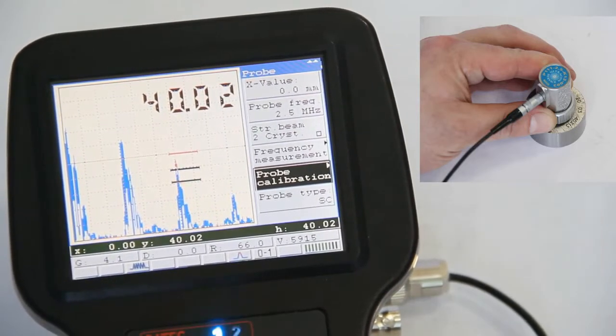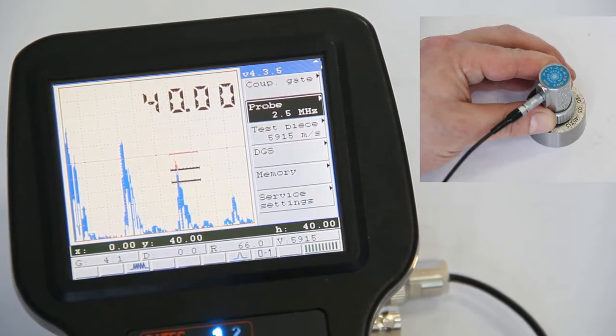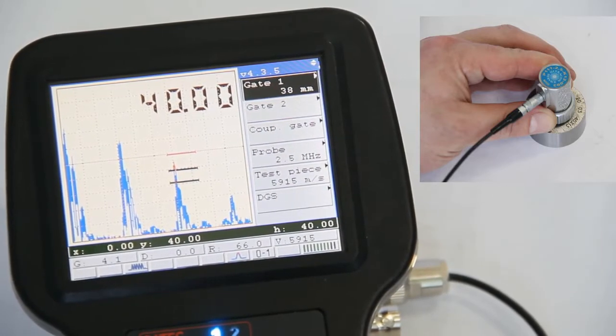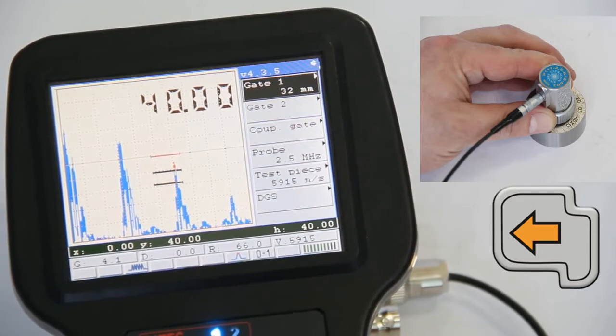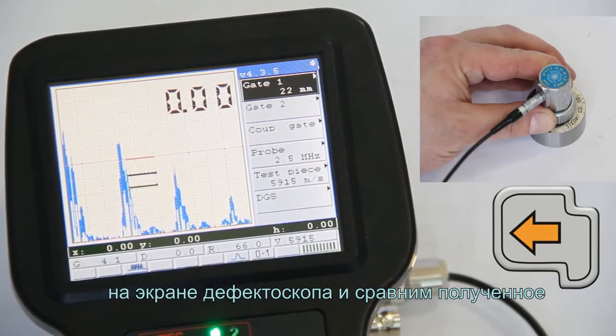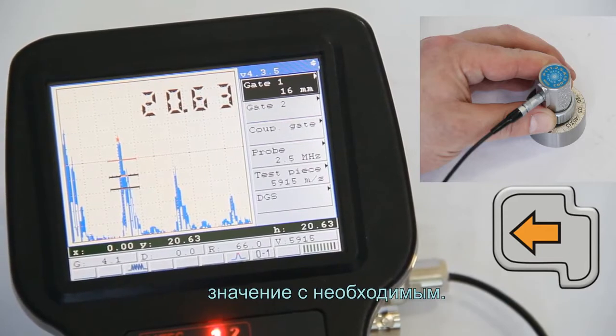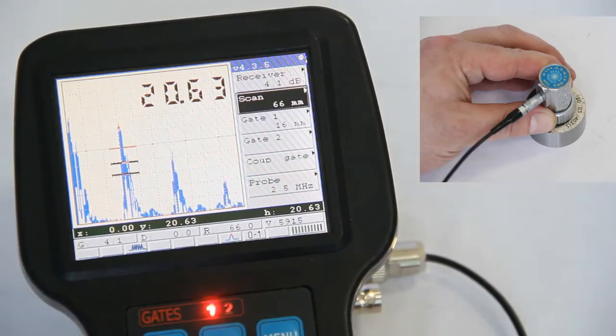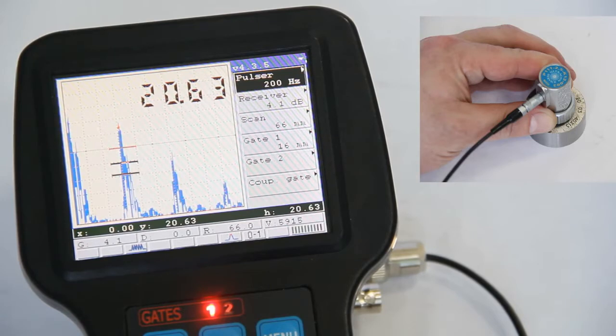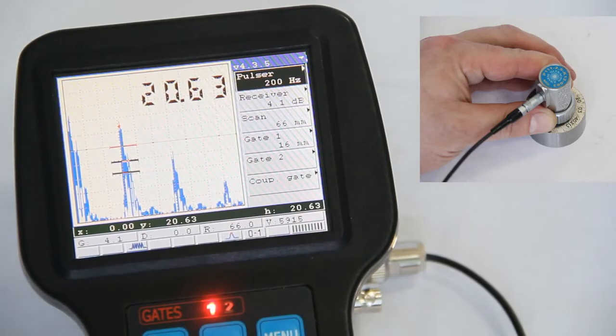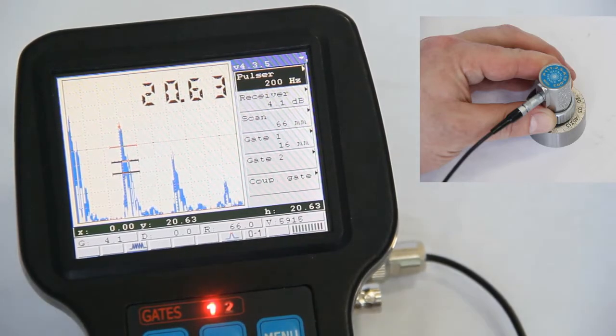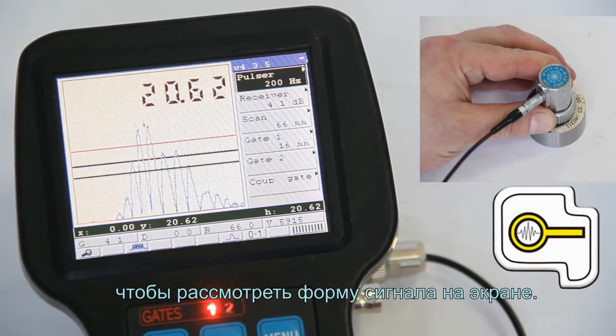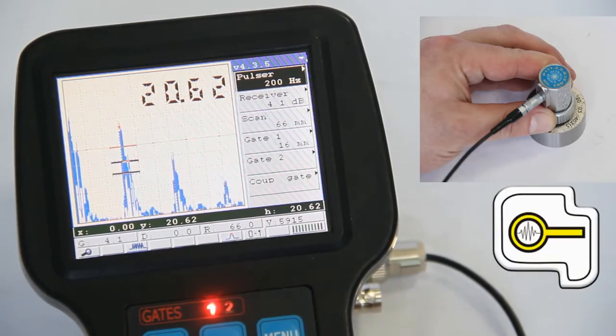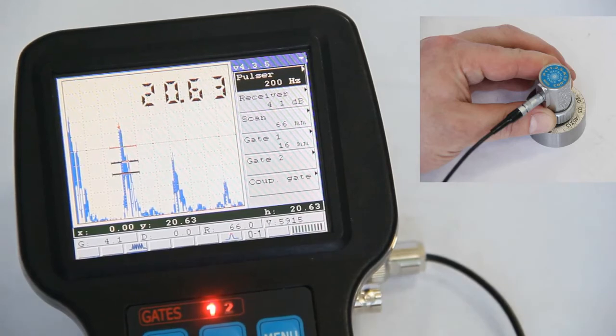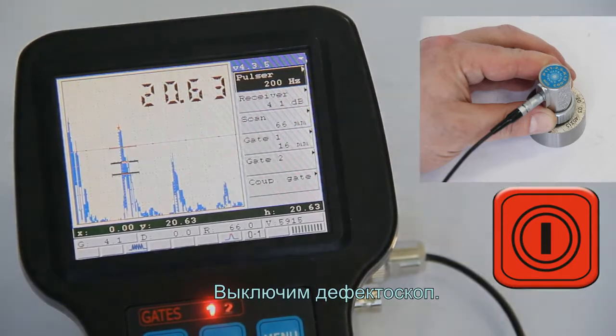Having set up the required gain value, move the gate to the first signal appeared on the flaw detector screen and compare the received value with the required one. Use electronic magnifying glass key for detailed examination of the signal shape on the flaw detector screen. Switch off the flaw detector.